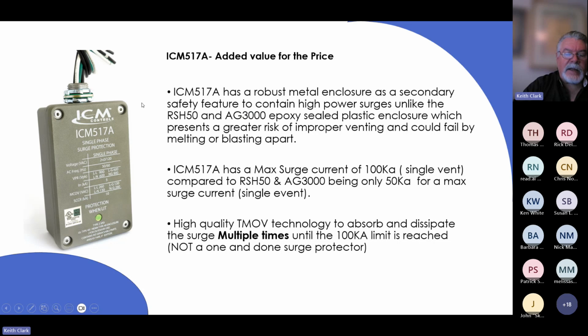So value added in ours compared to some of the competition, it has that robust metal enclosure, which is really a secondary safety feature to contain high power surges. So unlike some of the competitive models, RSH50, a lot of people recognize the Rector Seal and the AG3000. These are epoxy sealed plastic enclosures, which may present a greater risk of improper venting. So when there's a catastrophic type of event, like let's say it's a really big surge that is capable of really causing some damage to one of those TMOVs, that energy needs to go somewhere, and it needs to be able to vent and go somewhere.